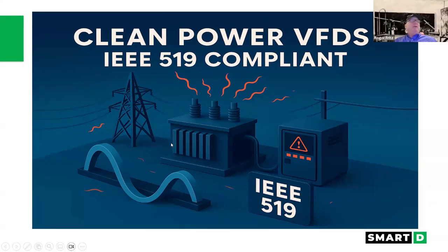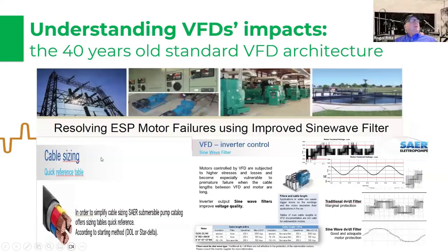There's actually in Southern California a massive generator system. It's a motor generator system where they draw on the load, and what that does is that inductive load of those giant motors down there, and then they're running it back to generators, cleaning up the waveform that's being created by some of the power quality issues that are out there with solar and wind, because they're not producing the same linear power. They're producing nonlinear power, not producing pure sine wave like the old generators did. So from that, you get issues, and there's different things that have been done for quite some time.